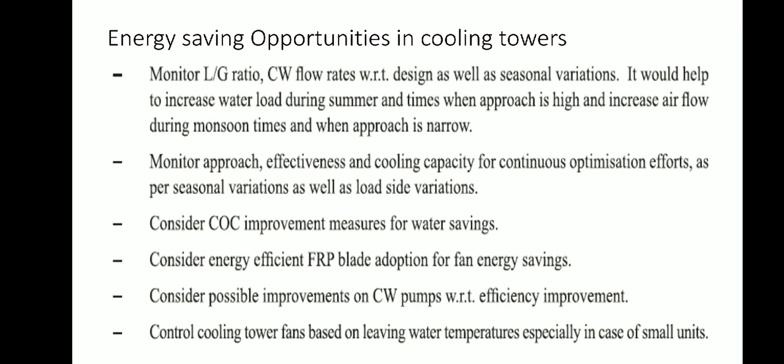periodically and monitor approach, effectiveness and cooling capacity for continuous optimization efforts as per seasonal variation as well as load side variations. Consider COC, which is cycles of concentration, improvement measures for water savings. Consider energy efficient FRP blades adoption for fan energy savings. Consider possible improvements on cooling water pumps with respect to efficiency improvement. Control cooling tower fan based on leaving water temperature, especially in case of small units.